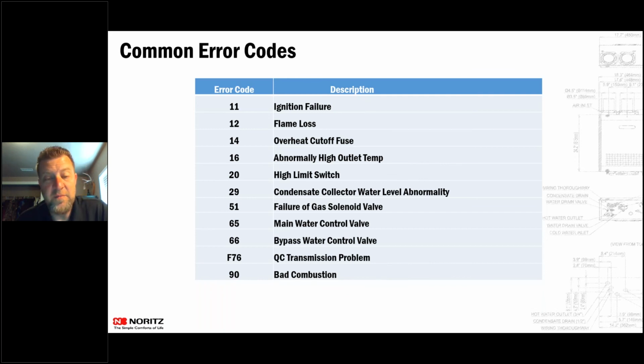And then the most common error code that we see all the time is 90, for bad combustion. A 90 just means that your combustion air coming in is not sufficient, or it's not getting enough combustion air. So that's when you would want to check that combustion air, and check whether something is blocking it.